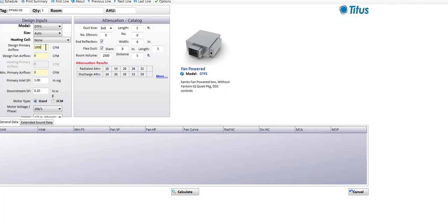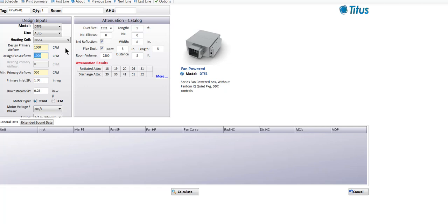In a series fan box, it's typical to have the design primary air flow matched to the fan air flow, which is what our program assumes. The only time you'd want a difference is if your primary air flow was colder than 55 degrees — for instance, if you had 40 degree low temperature air coming in and wanted to blend with return air to bring up the leaving air temperature. But in 99% of applications, you would see the same airflow for the design primary and the fan.